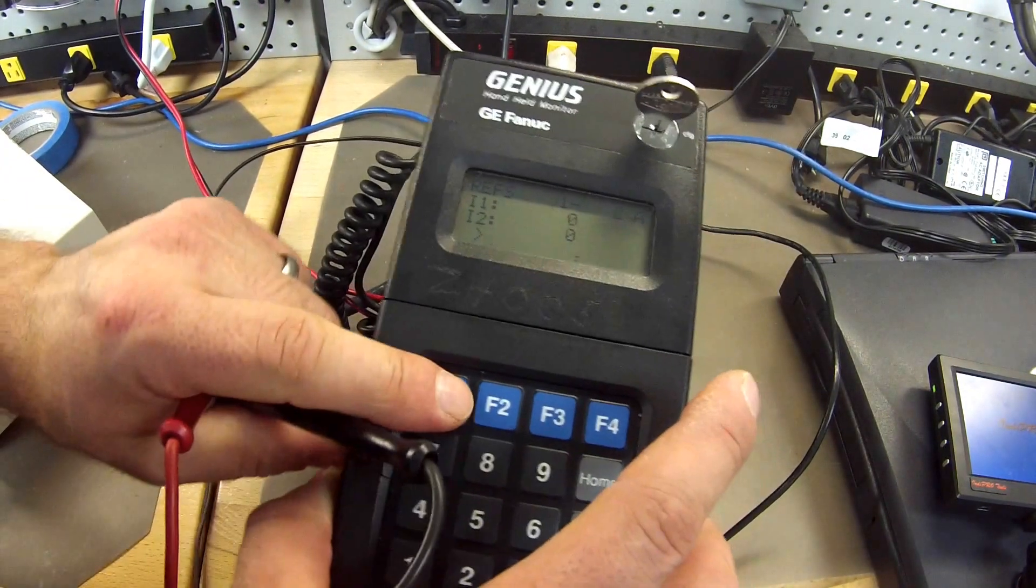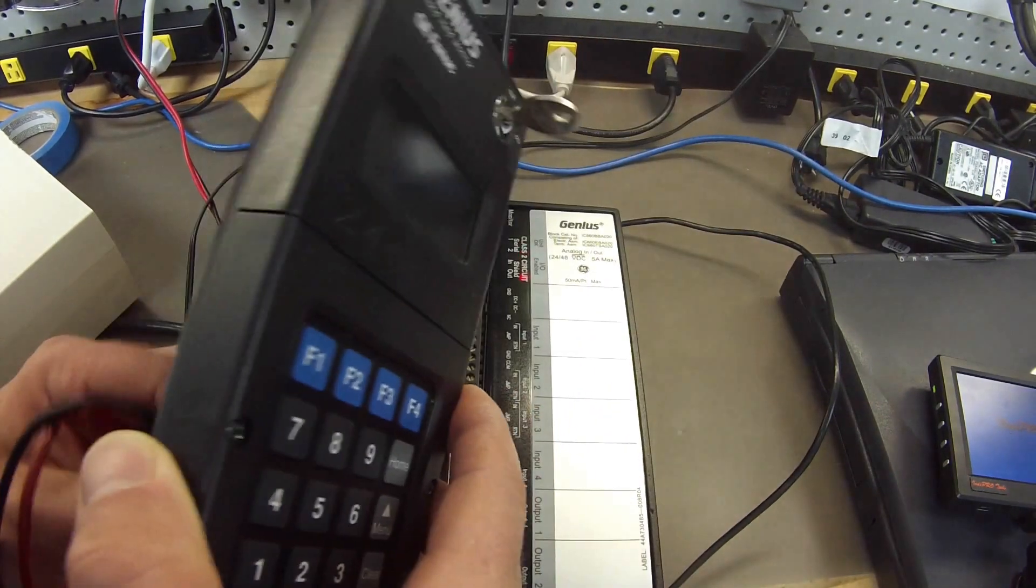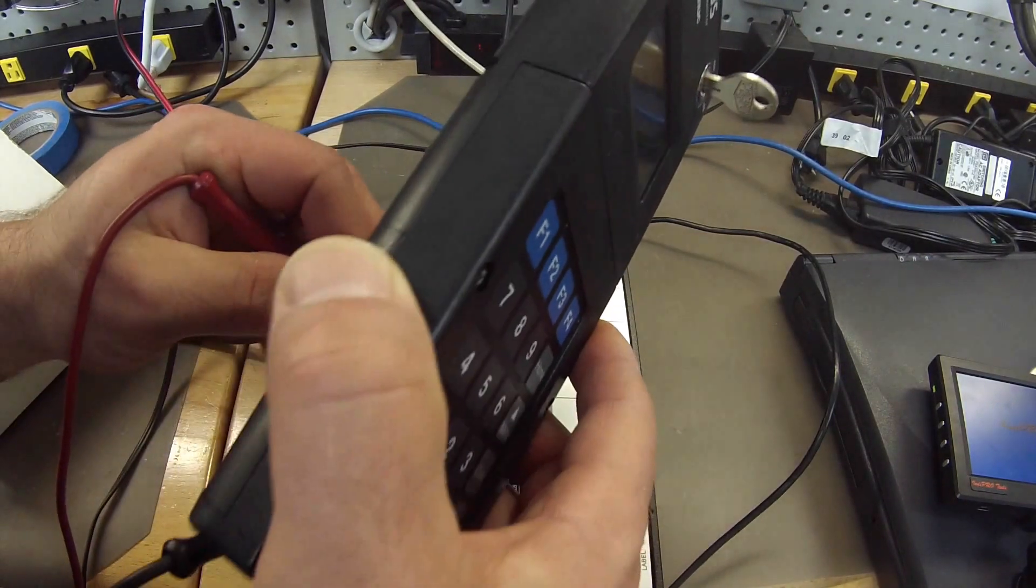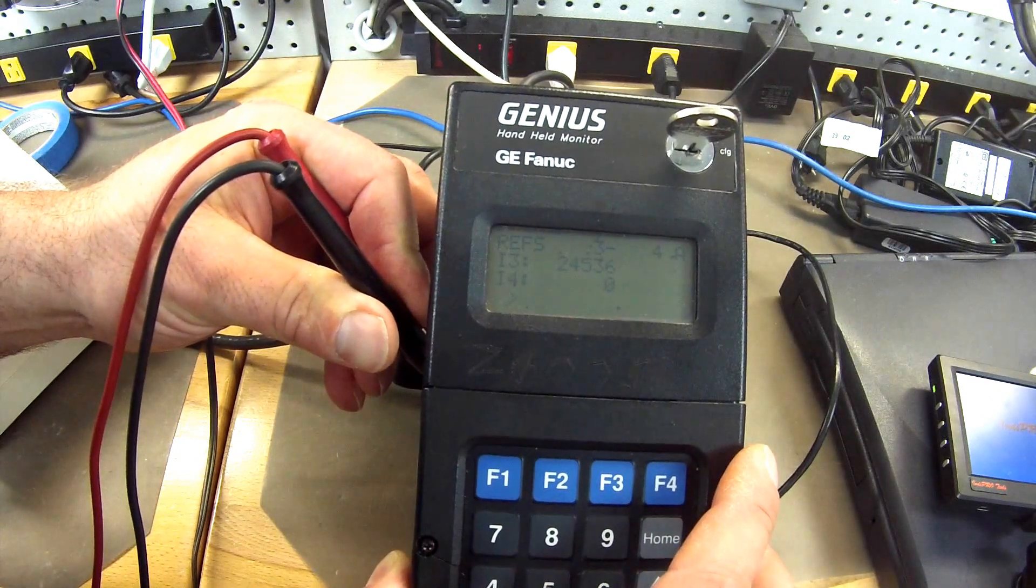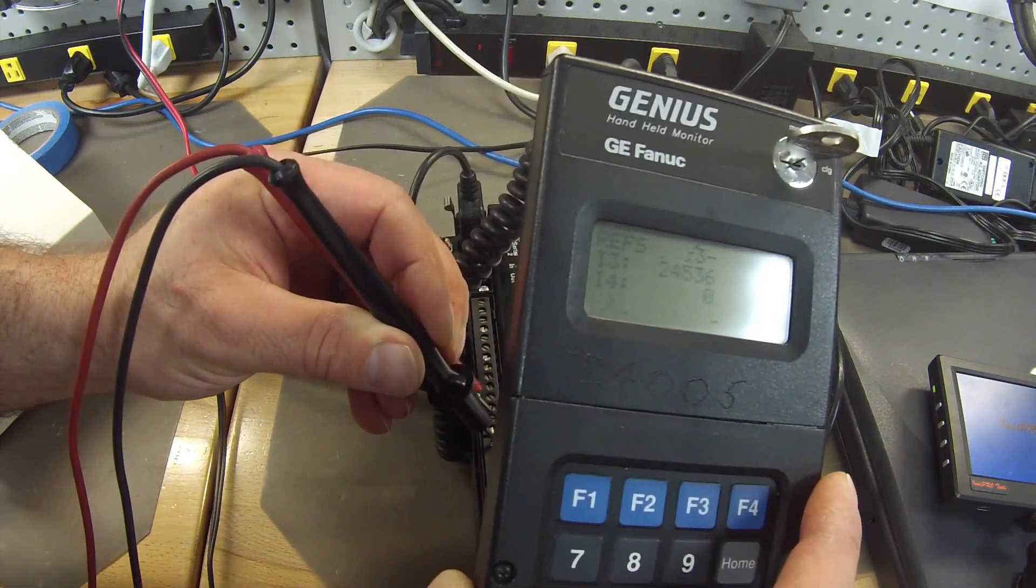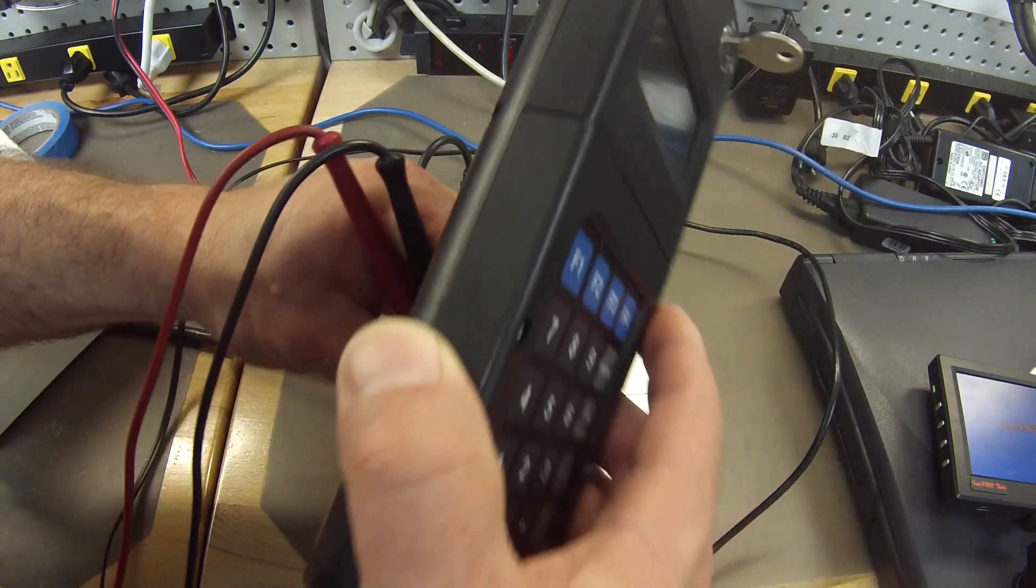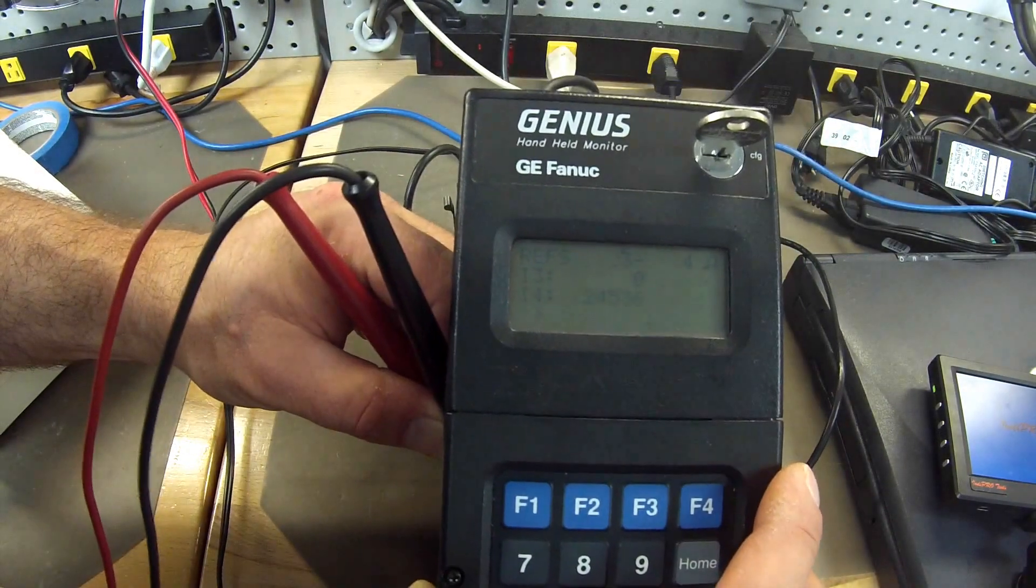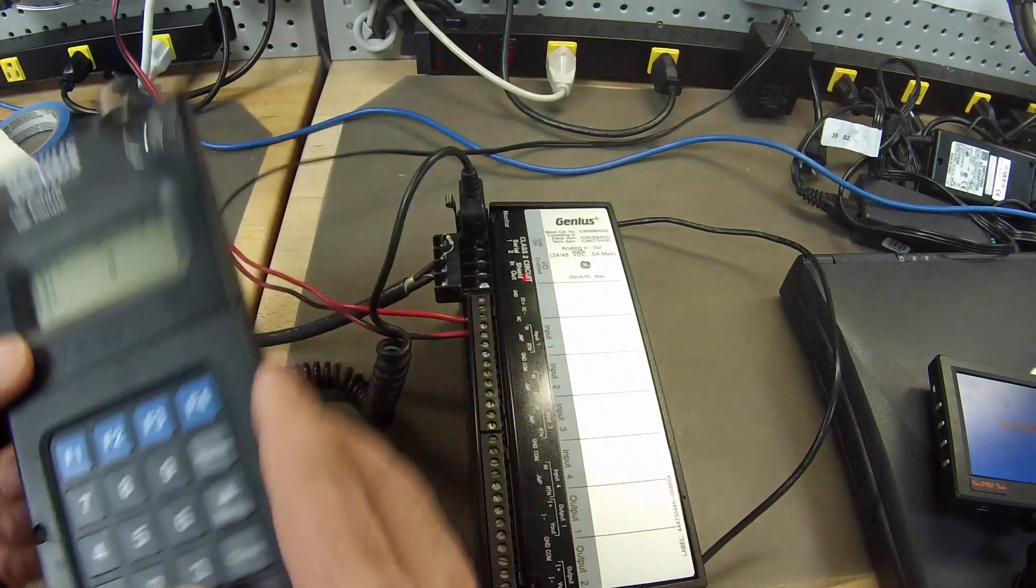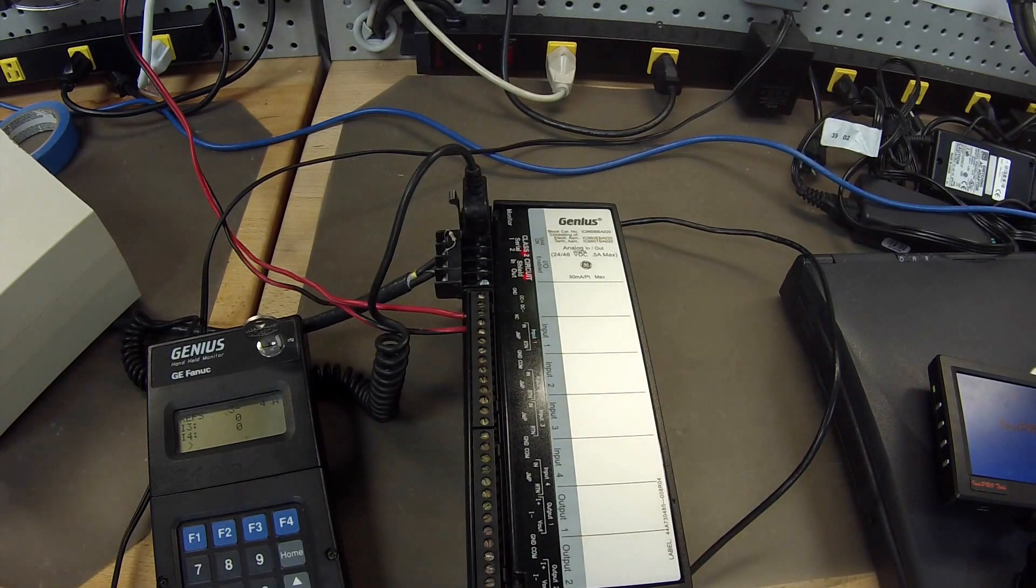I am going to toggle using F1 to my inputs 3 and 4. Input number 3, 24,536. Still definitely within the range. And input number 4, 24,536. That is good. That is a very consistent number since we want to see. Again I have factory scaling. Please keep that in mind.